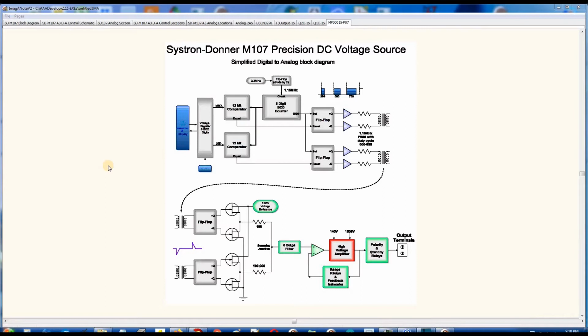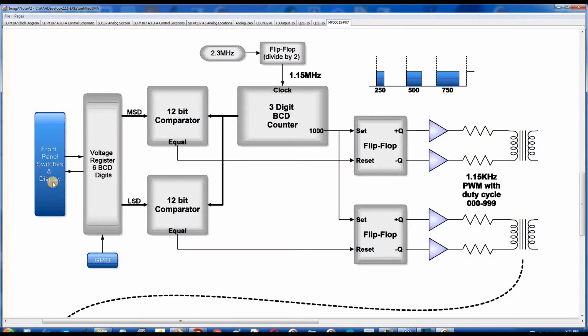So here's a block diagram of the beast. This is simplified, of course, and it's more complex than this, and it's not exactly like this, but it's close enough. So there's two major sections. There's a digital section and an analog section, and they're connected via pulse transformers, which allow a signal to get across, but electrically isolated. So looking at the digital part first, we've got the front panel switches and the display, which we can enter those 6 digits into, and it gets into this register. And that register can also be loaded via GPIB from a remote source.